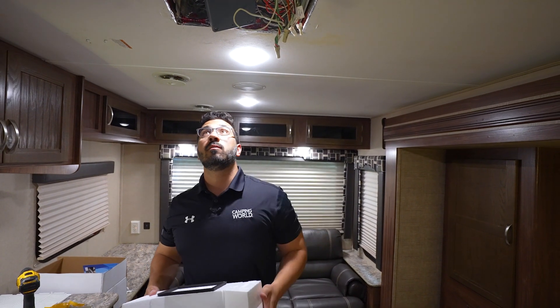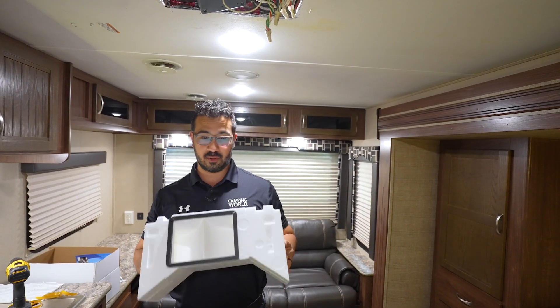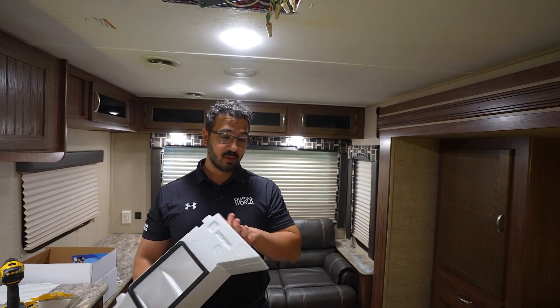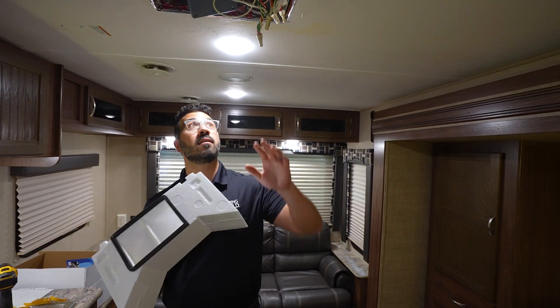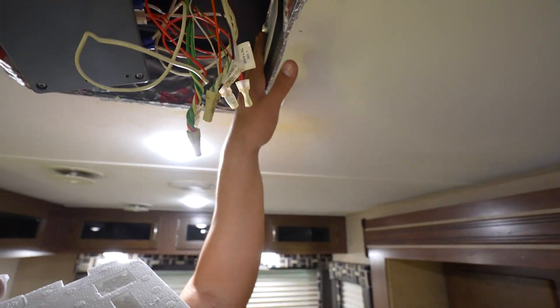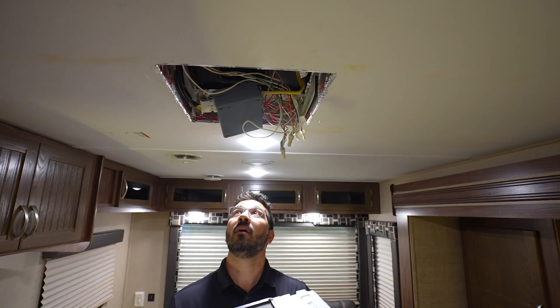With our duct adapters in place, it is now time to install the airflow system. On the Brisk 2, this is what it looks like — we have our flange here, and you can see it will disperse the air right into the ducts. To do this, you basically want to put it in on a 45-degree angle. Use the center point to try to move the AFS up, and then once you get up past the ducts, you're able to turn it and slip it into place.